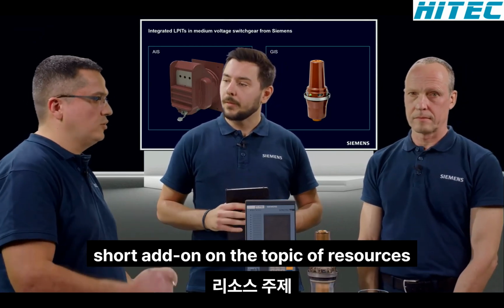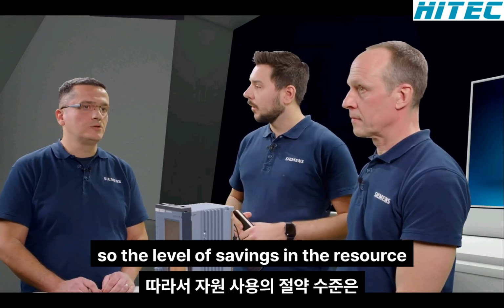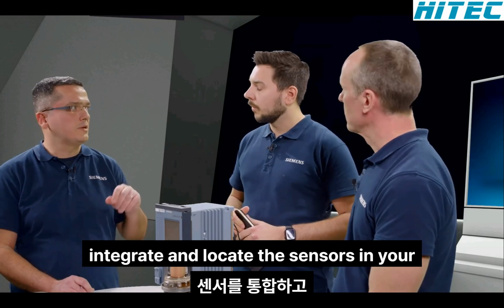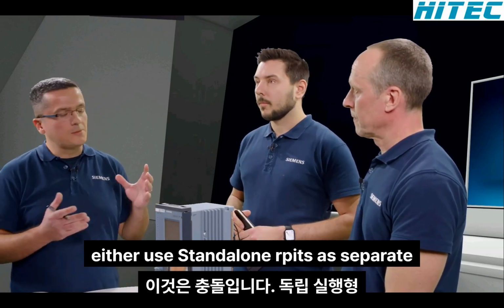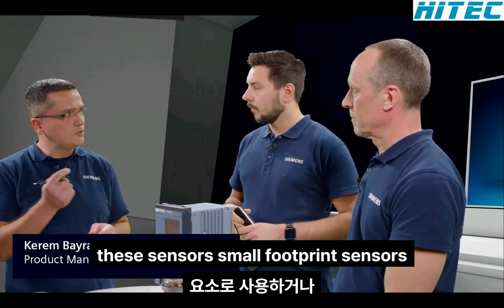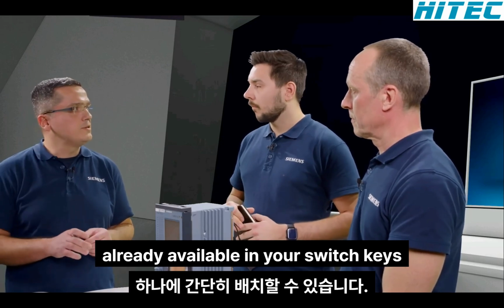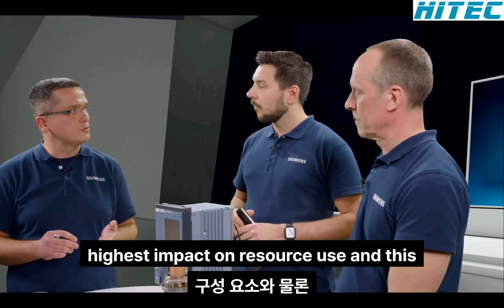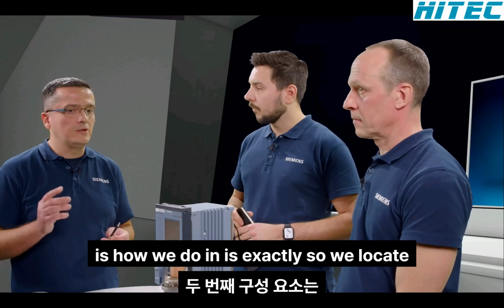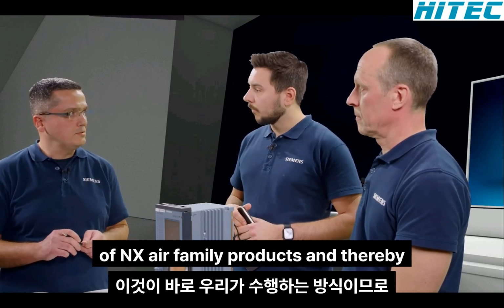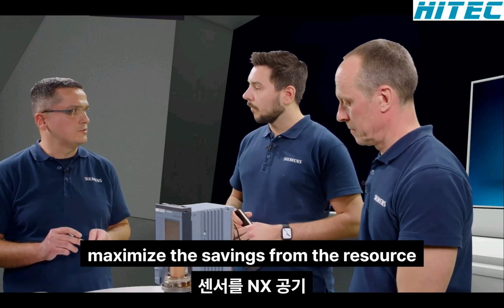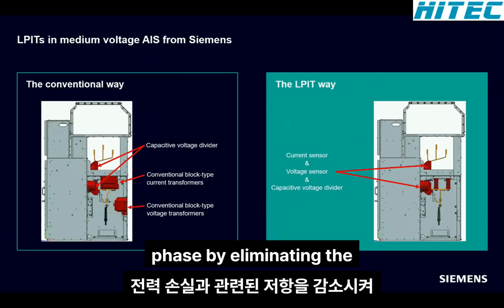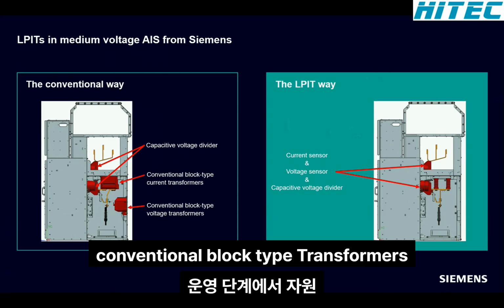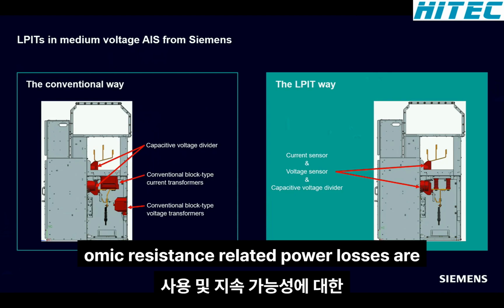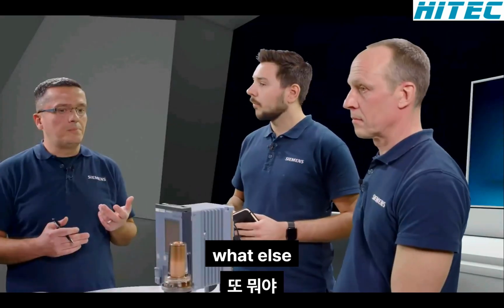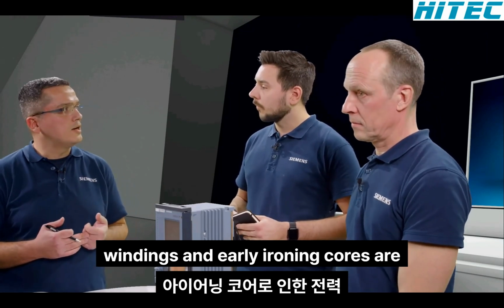Absolutely, yes. But let me have a short add-on on the topic of resource use. Sure. So the level of savings in the resource use has a direct relation on how you integrate and locate the sensors in your application. This is clear. You may either use standalone LPITs as separate components, or you can simply locate these sensors, small footprint sensors, into one of your existing components already available in your switchgear. And of course, the second one has the highest impact on resource use. And this is how we do in AIS exactly. So we locate the sensors into the existing bushings of NX Air family products, and thereby maximize the savings from the resource use. And coming back to your question about the sustainability in the operating phase, by eliminating the conventional block type transformers, ohmic resistance related power losses are being reduced. What else? Power dissipation due to secondary windings and iron cores are being fully eliminated.